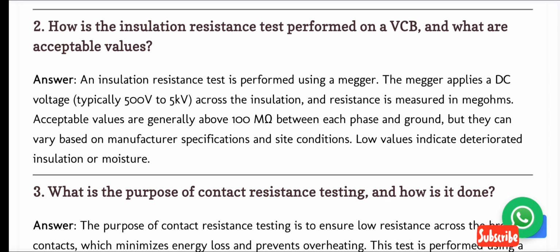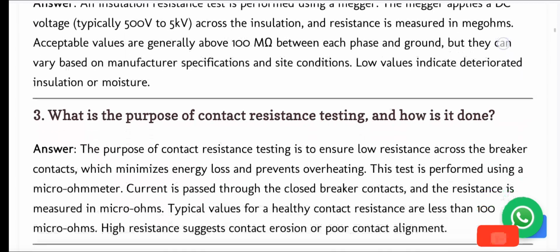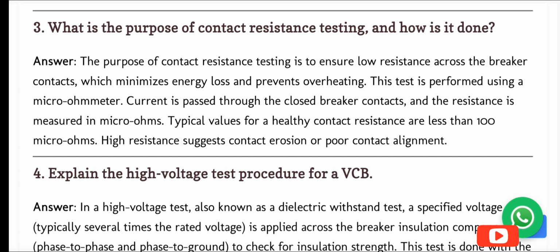Answer. An insulation resistance test is performed using a megger. The megger applies a DC voltage, typically 500 volts to 5 kV, across the insulation, and resistance is measured in megohms. Acceptable values are generally above 100 megohms between each phase and ground, but they can vary based on manufacturer specifications and site conditions. Low values indicate deteriorated insulation or moisture. 3. What is the purpose of contact resistance testing, and how is it done?